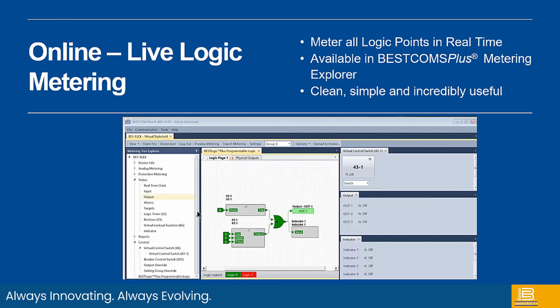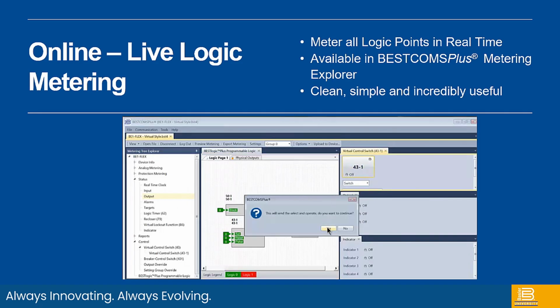The graphics are 100% identical to the settings. So when somebody creates the settings, they have additionally automatically created this live logic view, and I'll just press play to give a quick example of what this live logic does. In this example, I've got an overcurrent 50-1 and a switch 43-1 that are tied to an OR gate and an output. So I'm going to manually operate that 43 and watch it go through the OR gate, and therefore watch the output operate. So if and when this is in front of a physical relay, you would actually hear that physical output operate because that's what's happening in this particular chunk of logic.